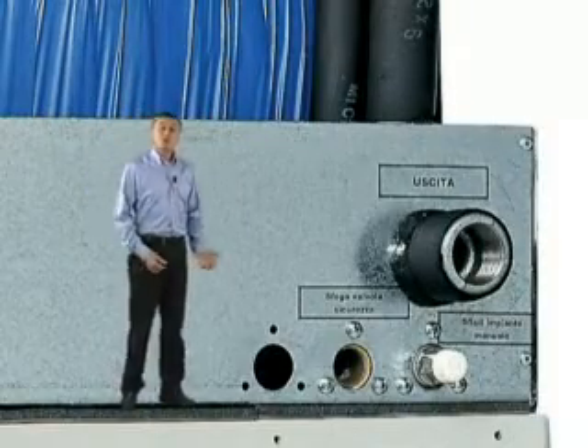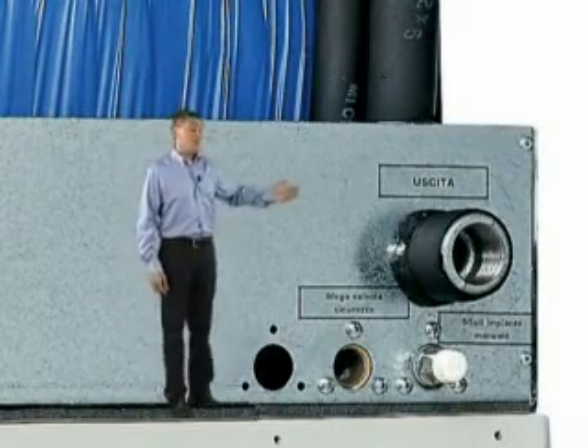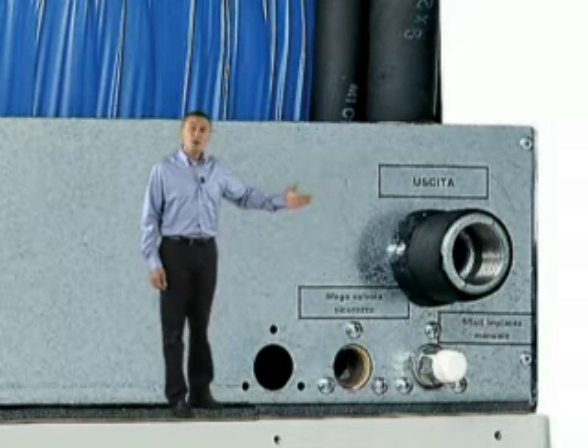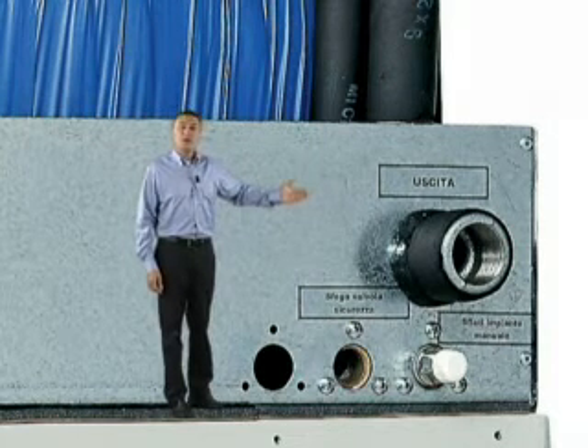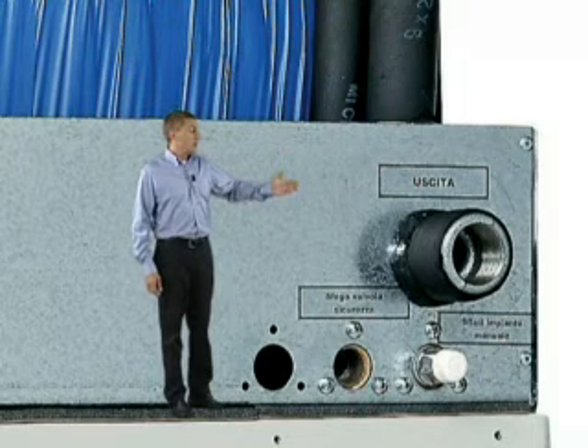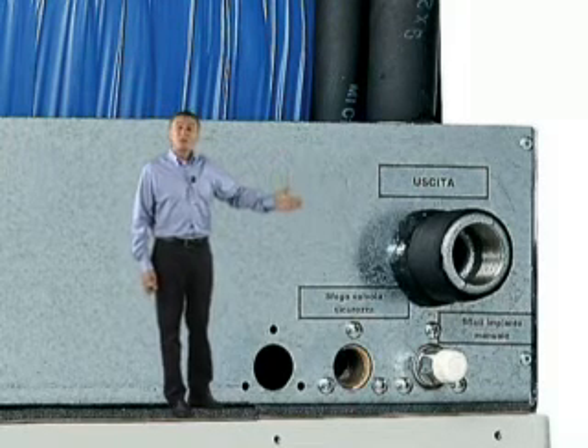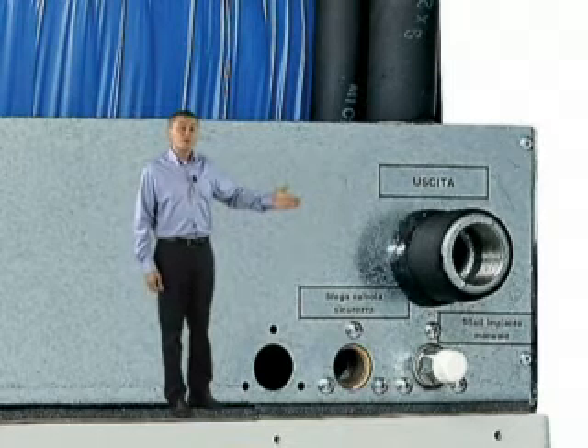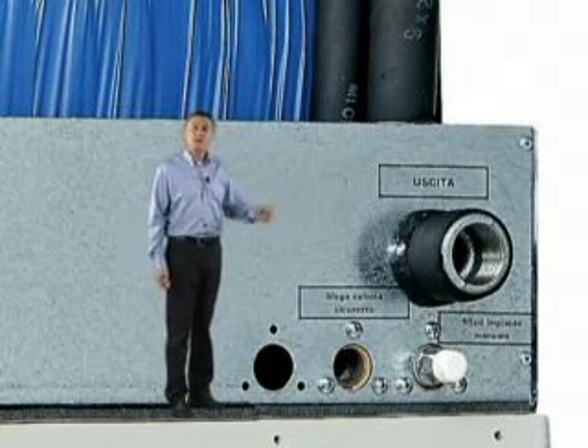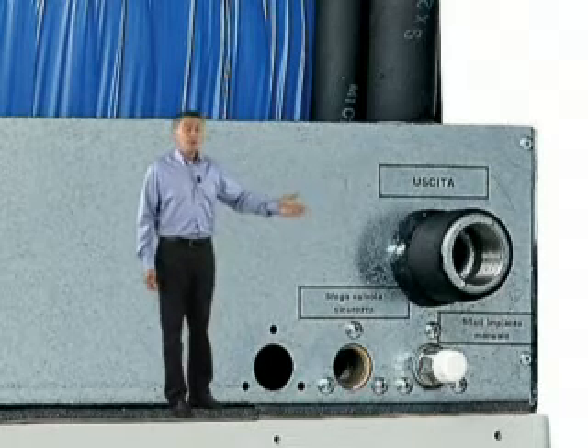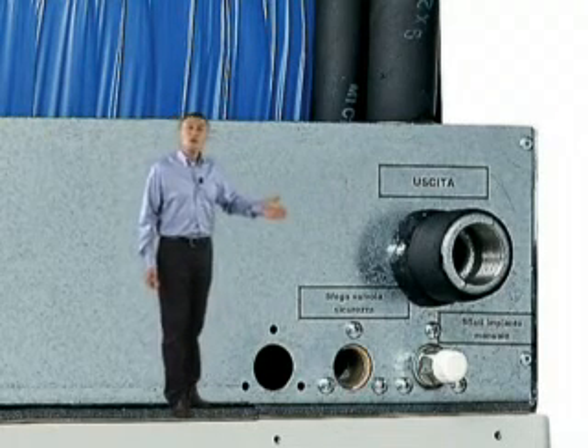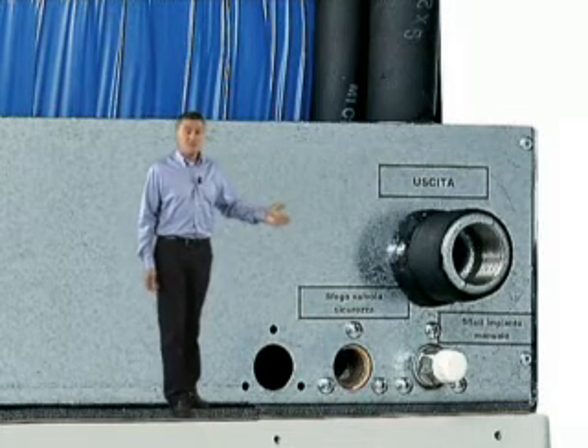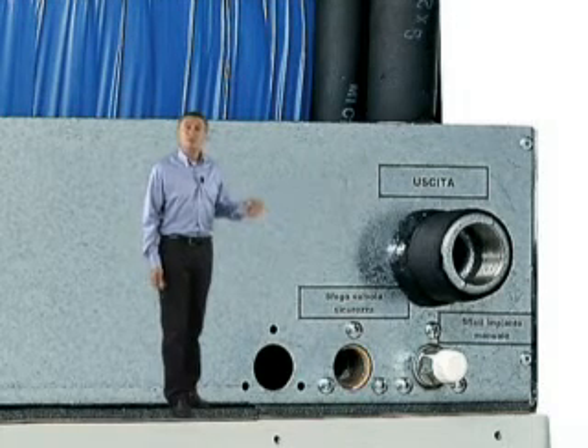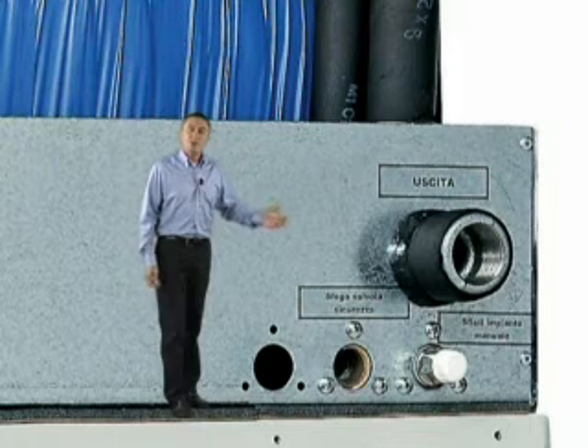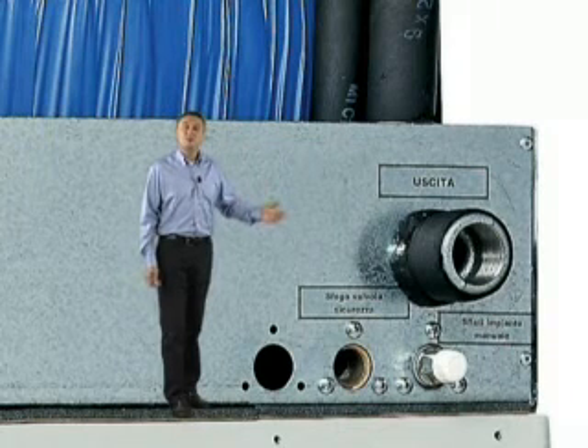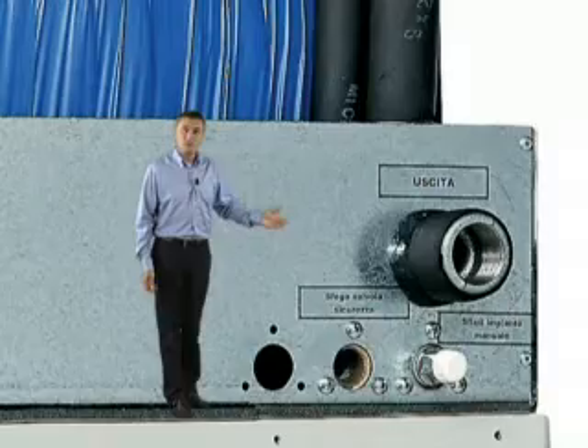We now move to the other side of the machine to see the water outlet connector, where it is connected to the internal part of the fan coil. We notice that under this connector there is another bleed for the discharge of water and in particular of air. To one side we find an automatic safety valve with the job of discharging Climabox water in the event of an emergency caused by an internal system pressure that is too high.